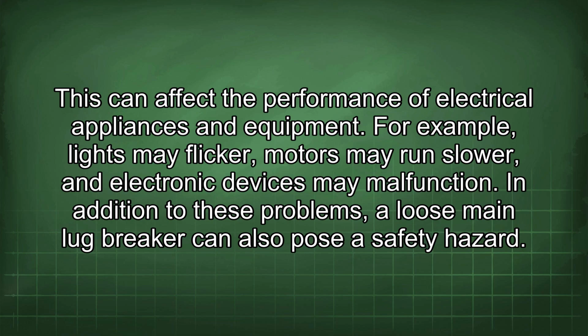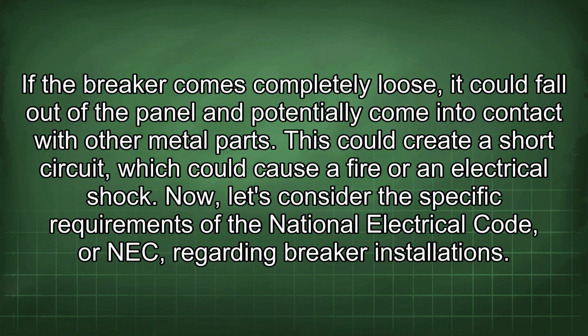In addition to these problems, a loose main lug breaker can also pose a safety hazard. If the breaker comes completely loose, it could fall out of the panel and potentially come into contact with other metal parts. This could create a short circuit, which could cause a fire or an electrical shock.